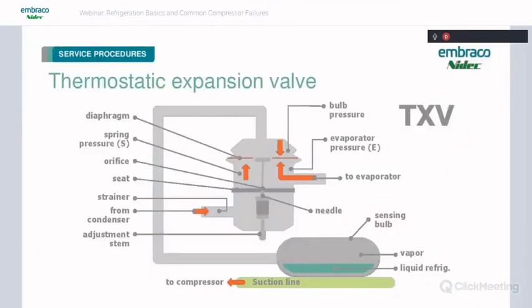Speaking of TXV valves, we say that you want to use subcooling to charge a TXV equipped system. And this is because TXV valves have the ability to close or open the orifice, metering more or less refrigerant to the evaporator. This means that they can compensate for a little too little or a little too much refrigerant. So they're actually attempting to maintain the correct superheat, meaning the correct amount of refrigerant to the evaporator. And they do this by mounting a vapor bulb, a sensing bulb, on the suction line coming out of the evaporator.